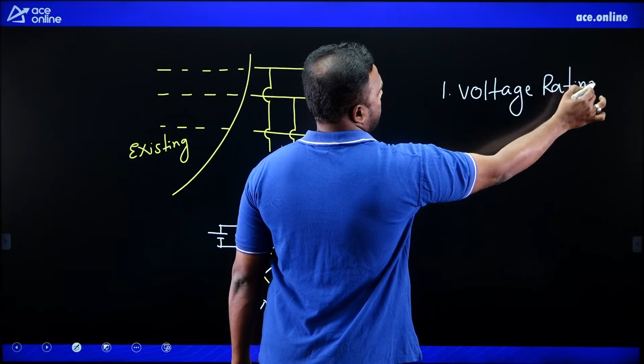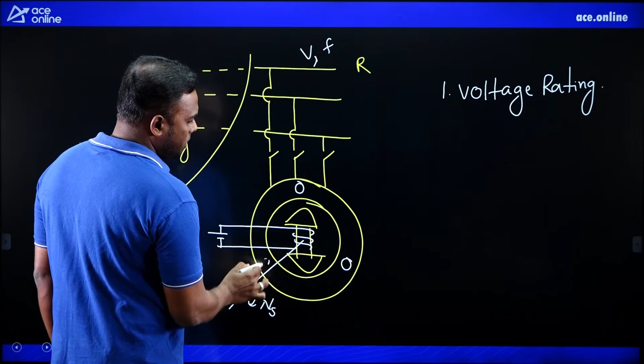to connect in parallel. Suppose you are connecting to the bus bar, and the bus bar has some voltage V and frequency F. Now this alternator also should generate the same magnitude of voltage. That is, if it is 400 volts, it should also generate 400 volts at that time. Now how to verify that voltage rating condition? The first condition is that the voltage rating of the alternator must be the same as the bus bar voltage rating. Whatever is there here, the same voltage should be there.